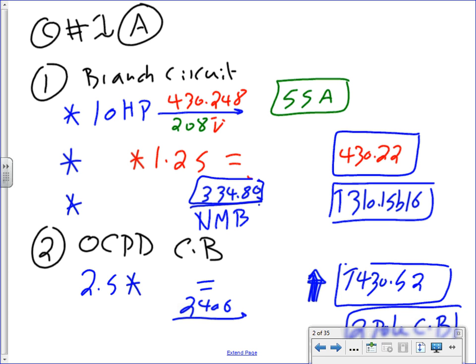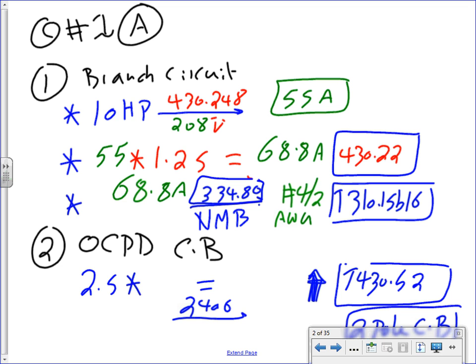Find the full load current first, and I'll give you enough time to write. After you find the full load current, here's my full load current. Multiply it by 1.25 because motors are assumed to be continuous load, and that will give you 68.8 amps. What's your reference? 430.22. Then you take the 68.8 amps to 334.80, the NM cable table, and that will give you a number 4 AWG NM cable. I want to remind you guys, we go to a 60-degree column here.